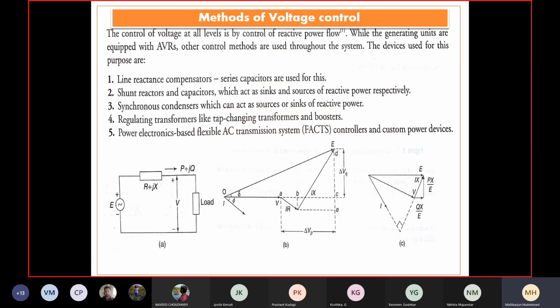The overall system being highly inductive, transmitting reactive power over a large distance imposes a lot of limitations and higher loss. Hence, transmission of reactive power over larger distances is not facilitated. It is discouraged. It is in fact to be compensated at the point of need or at the optimal point of the system, which is commensurate and can be accommodated in the system. Therefore, when there is a compensation for additional load or lagging VAR by the capacitor, and suddenly loads are removed, what will happen? In a highly compensated system, with the capacitor highly acting upon the system to compensate, if loads are suddenly removed, that leading VAR floats on the system. That will affect the system operation as well.